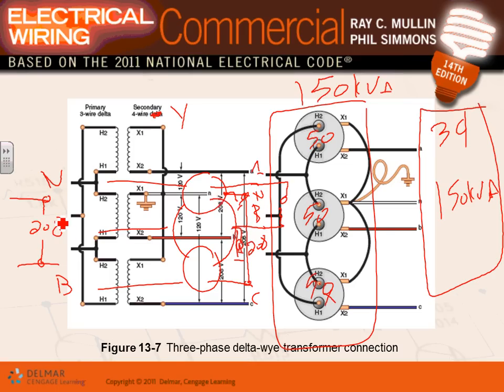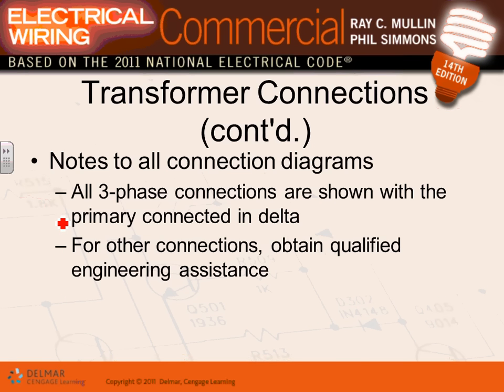If you bring a wire from the neutral to phase B on a center tap delta, you get 208, you shall not use it. If you bring a wire from phase B to the neutral, 208. From phase C to the neutral, 120. From phase A to the neutral, 120. So, good ones, guys, good ones. Only on phase B. You still, then, Adam, you still have phase C and phase A to utilize. Yeah. Only 120 if you go phase to neutral, but if you go phase to phase, you get 240.